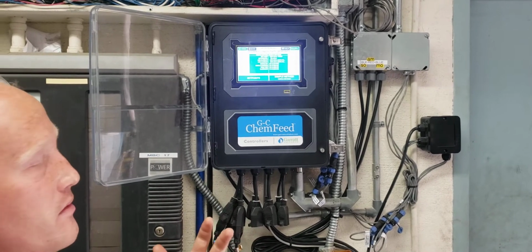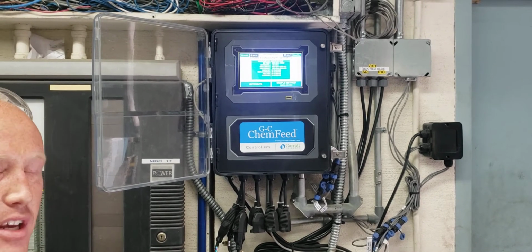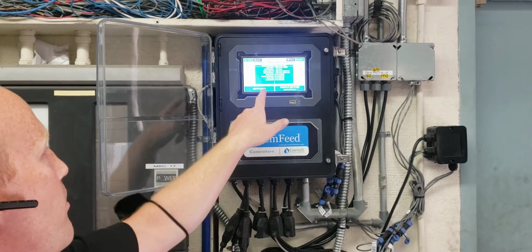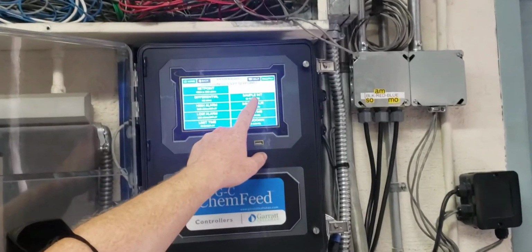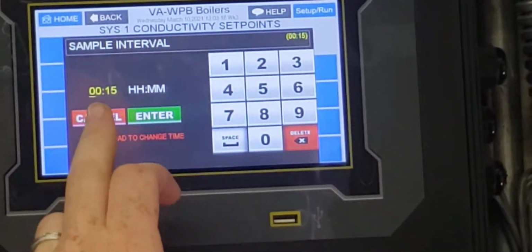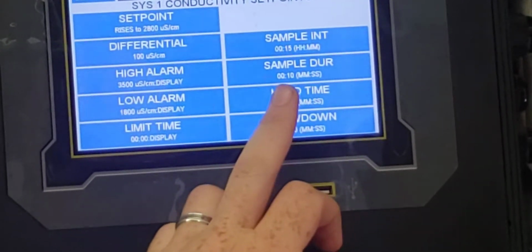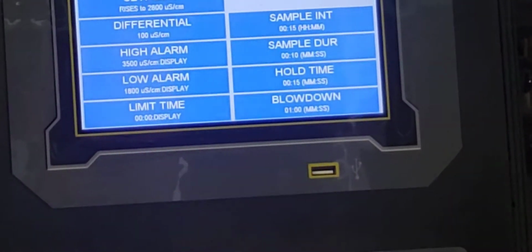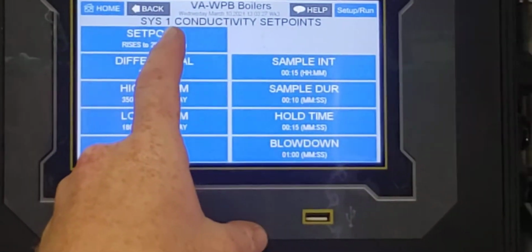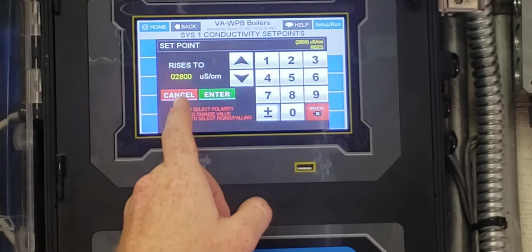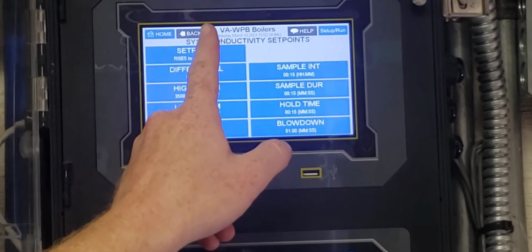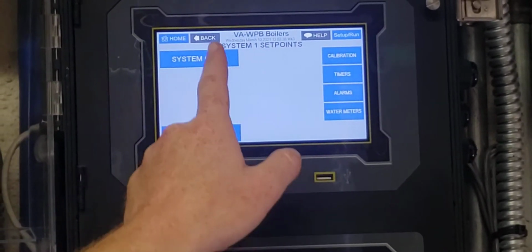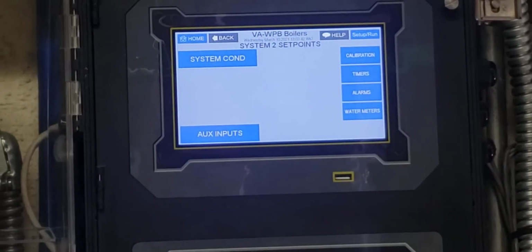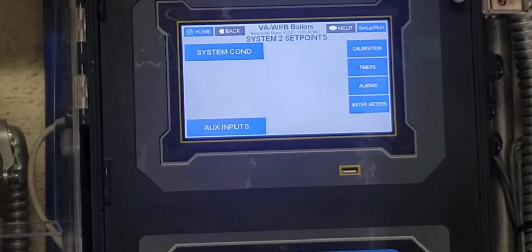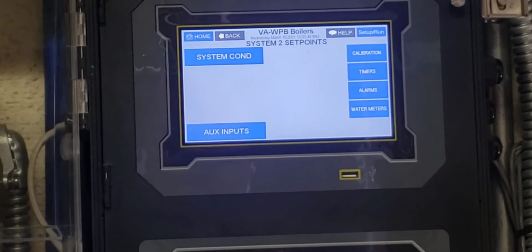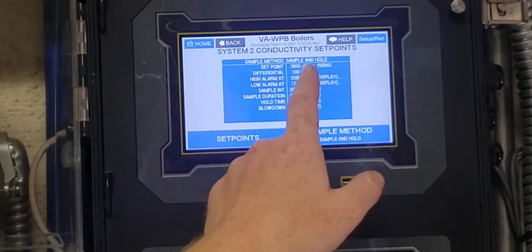And that is changeable. If we find it's not keeping up with that 15-minute interval, we can make adjustments. You can go to set points in the controller, go to sample interval and change it right on this screen, or the sample duration as well. Your conductivity set point is there too. Something else you have to pay attention to is that each system is for each boiler, 1, 2, and 3. If you make a change in system 1, it doesn't change it for boilers 2 and 3. You still have to go in and check it.